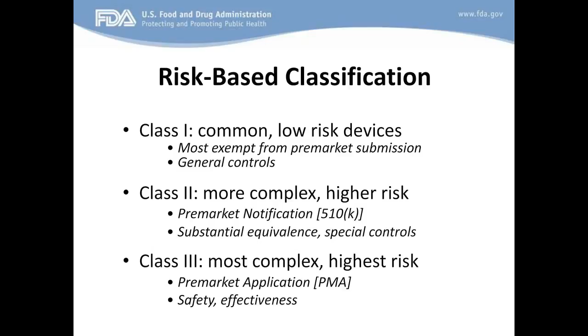So what are general controls? General controls are things that we expect most manufacturers to be able to do. That is, first they would have to register and list with the FDA so that the FDA would know that they are manufacturing or making and distributing medical devices. They would have to follow good manufacturing practices. They have to report device failures to the FDA, and they have to have a system for remedying the device failures. That is, they have to be able to fix those failures that they find.